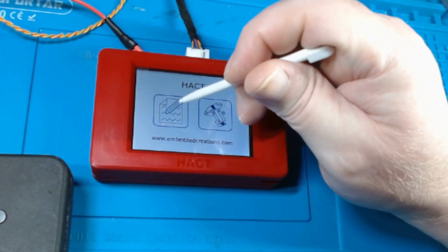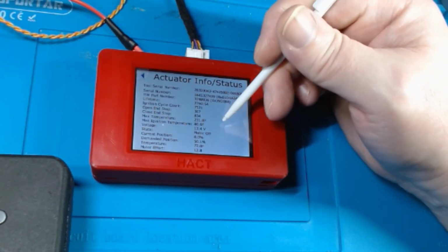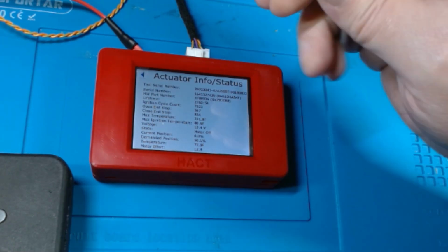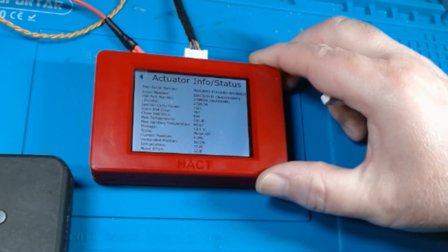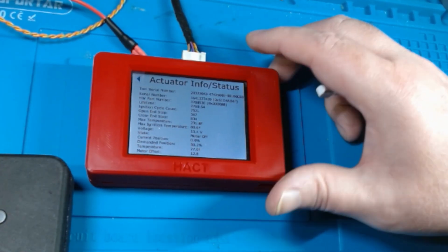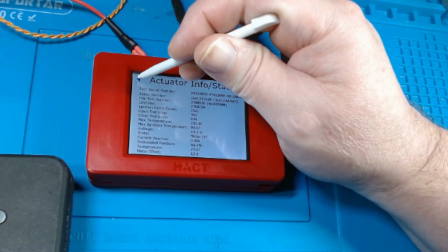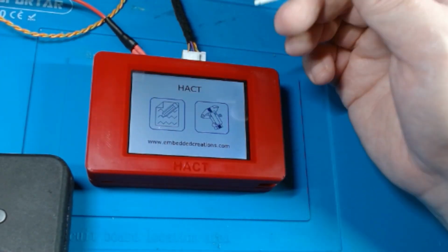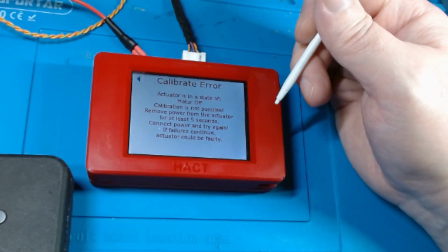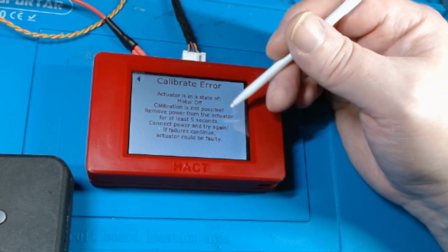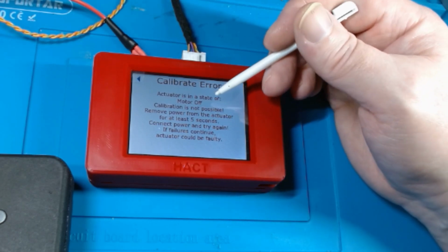So now if you look at the status or the state, you'll see the state is motor off. Well, when it's in a state of motor off, you can't calibrate it, or you're not supposed to, or the tool is supposed to prevent you from calibrating it because the state, or the calibration, is going to be incorrect.